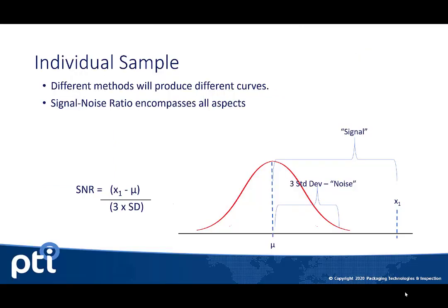So when we're comparing two different test methods, we have to ask ourselves, how do we really know when one method is better than another? It becomes very challenging if you have an attribute test method and you want to replace it with a quantitative test method. Attribute data is certainly not that valuable when it gets to statistical tools, and it doesn't allow us to really analyze the performance of that test in a way that a quantitative test method would.